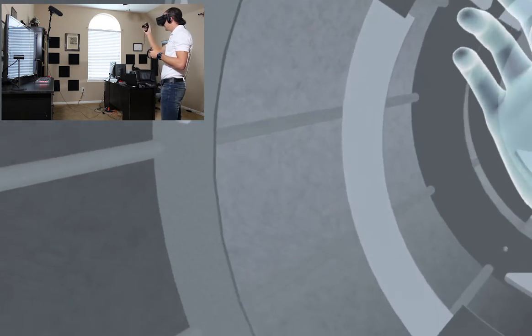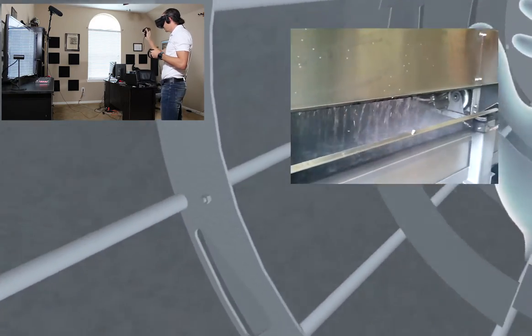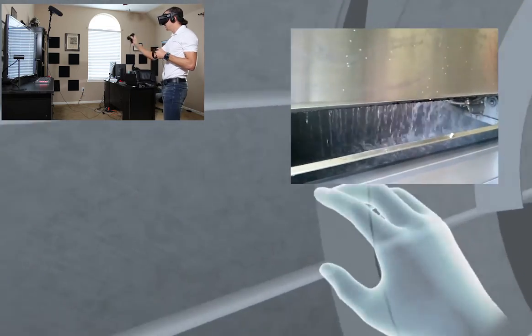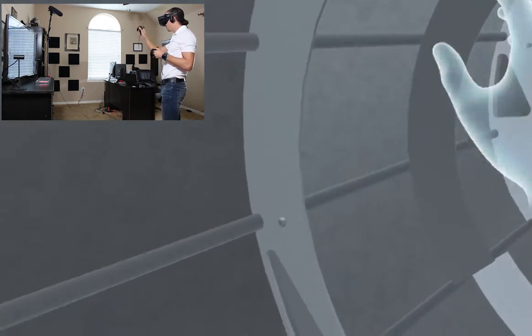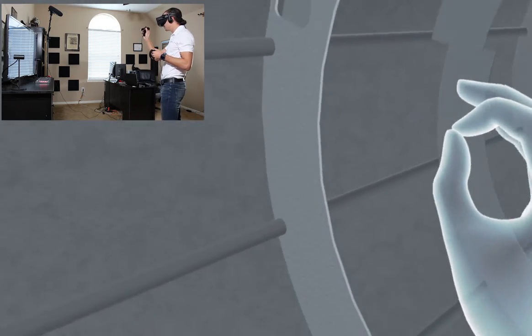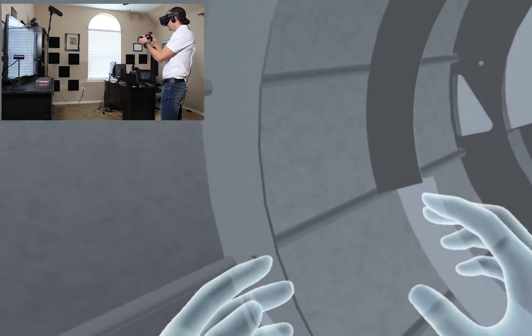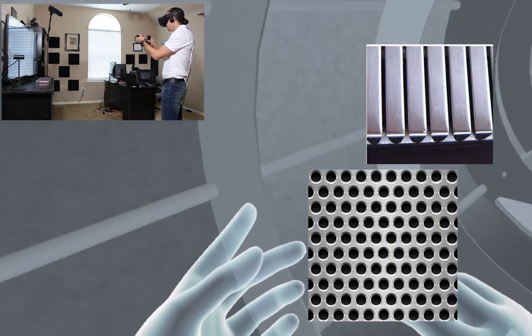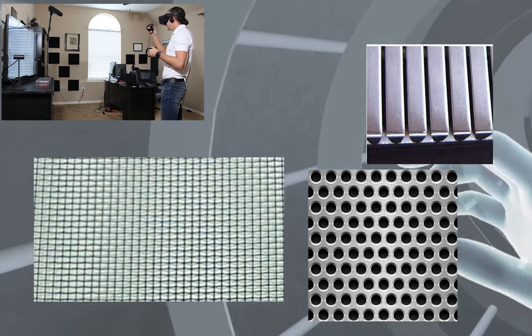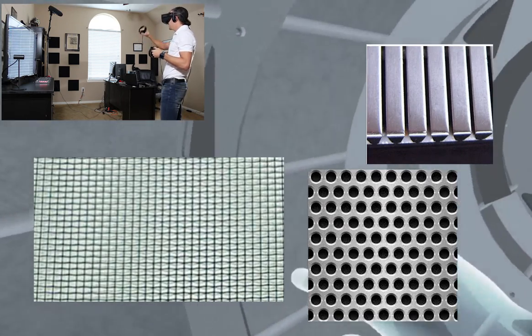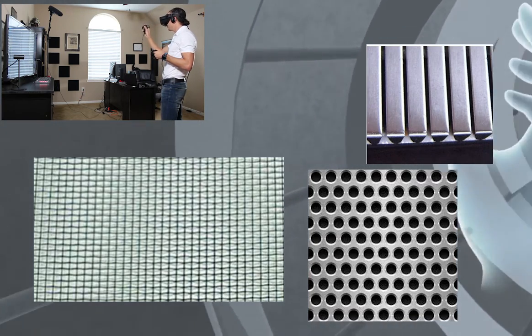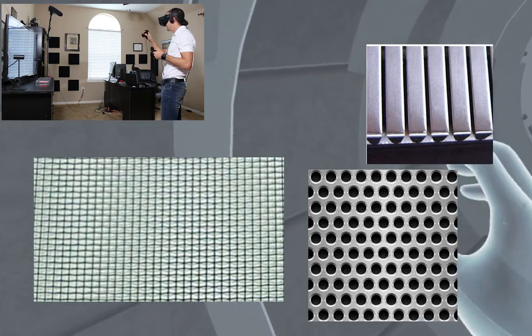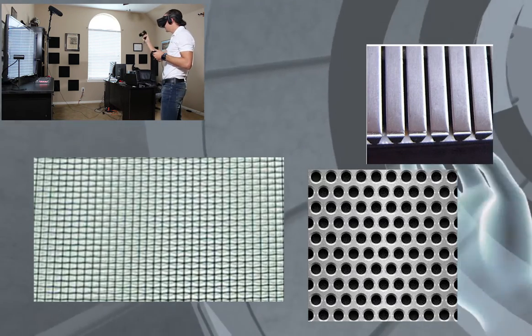Because we don't want to lose solids, and that's where we get a really clean filtrate. So what we're looking for is a material for this screening that is a large amount of overall open area, but very small individual opening sizes. And of the materials available that are typically used, we see wedge wire, perforated sheet, and woven wire mesh. It's very clear, and we'll have them displayed here in this video, that the woven wire mesh has a huge amount of overall open area, but has the smallest opening sizes.